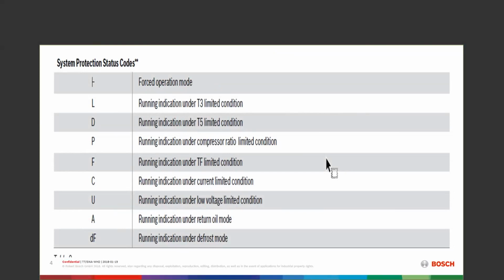It's kind of like that scenario that we talked about earlier today, in that I am needing 240 volts, but let's say we only have 195 volts to make this 3-ton unit run. It will give you what it can give you out of that 195, but when you get up there and you pull the cover, you will see a U, and then you'll probably see another type of number situation on the Hertz rating. So that is basically a limited situation.